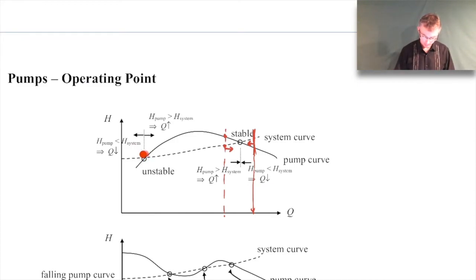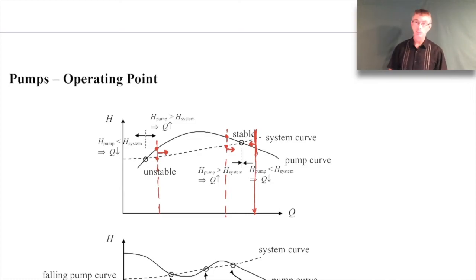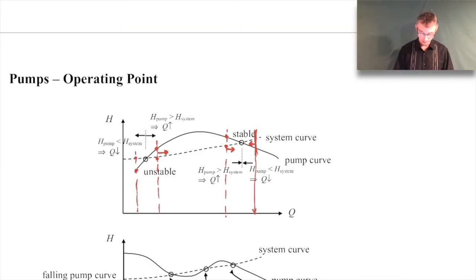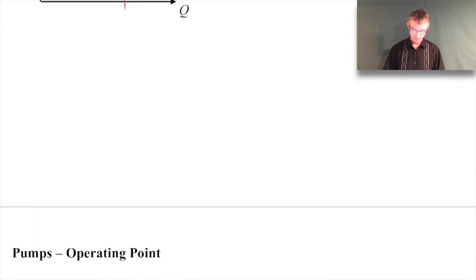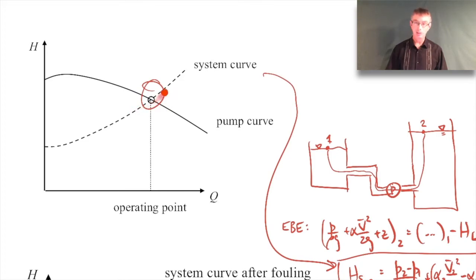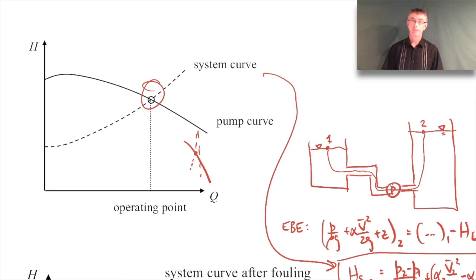Typically we would prefer to avoid these kind of multiple operating point scenarios. It's much better to have a situation where there's a clear single operating point. For stability purposes, you want the intersection to be as steep as possible - you'd like your pump curve to go steeply downward and your system curve to be steep as well. Because if you push to one side, there's a big difference between what your system needs and what your pump can provide, and it'll quickly push you back to that operating point.